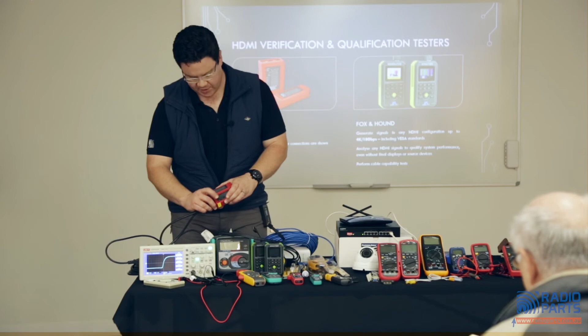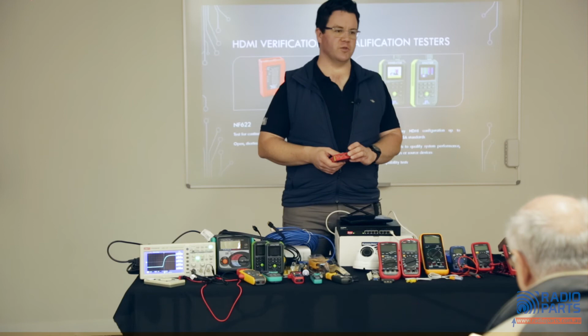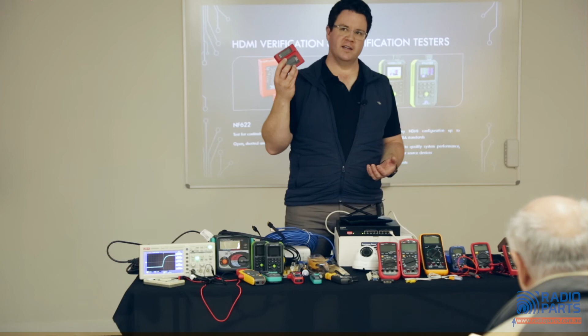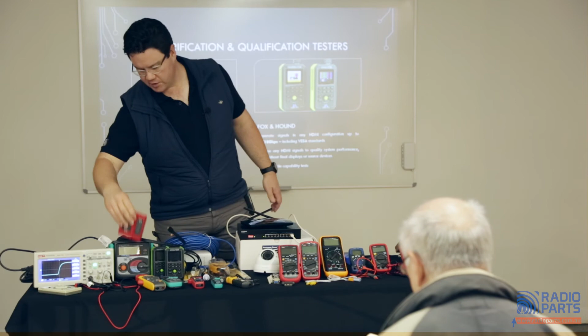That's fine. As a basic test, just to show that the lead's not damaged or dead, this is a really useful little thing. You should be testing cables out with something like this, even in a domestic and basic setting. If you're running a cable through a wall, a little 5-meter or 3-meter cable, plug it into this and go, copper's connected to copper, we're all good. I've used this before to find where a cable was run through a wall and was damaged after installation because the plasterers went through and crammed it in together, and the cable started to fail and cause problems. So a simple test is enough for that kind of job.